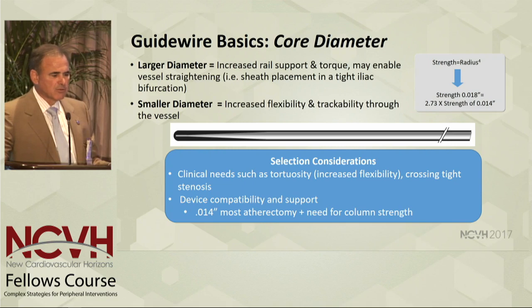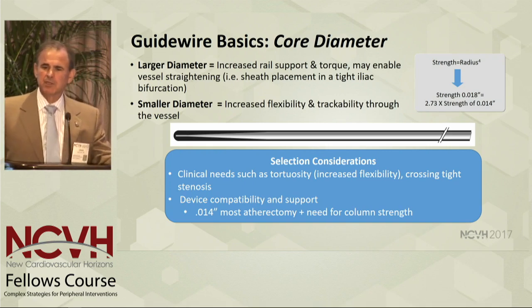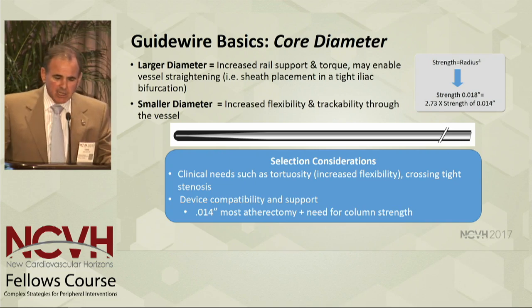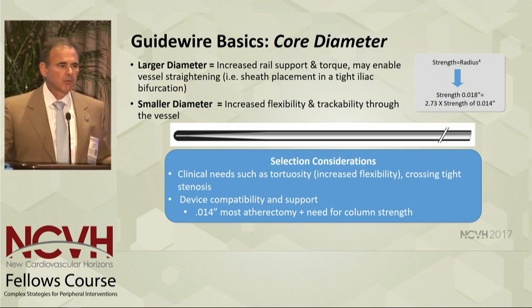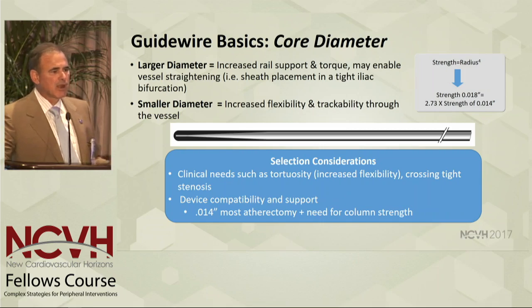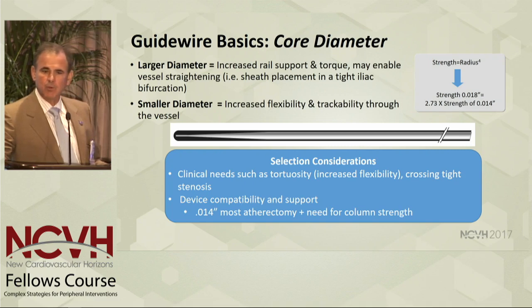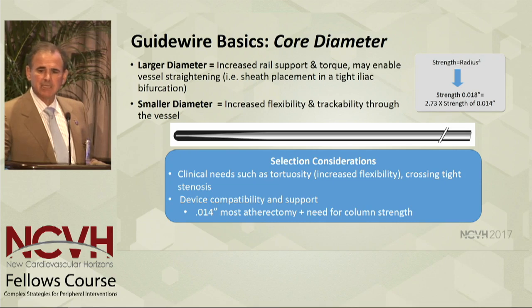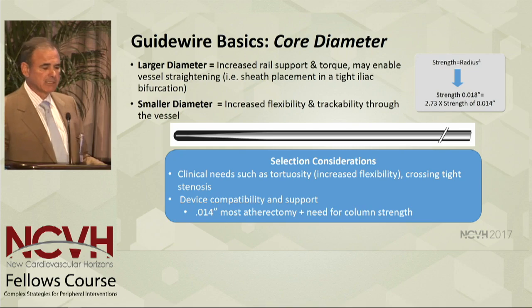The smaller diameter of the wire, the better will be the flexibility and the trackability through a vessel. I hear often people say, what really is the difference between an 018 and 014 wire? Since the columnar support and torque is related to the fourth power of the radius, an 018 wire, if made of the same construct, would have 2.73 times as much torque or columnar shaft support. This is widely misunderstood in the field. Many devices that we use are only compatible with 014 wires, so it's important to understand how we maximize flexibility and ability to cross.